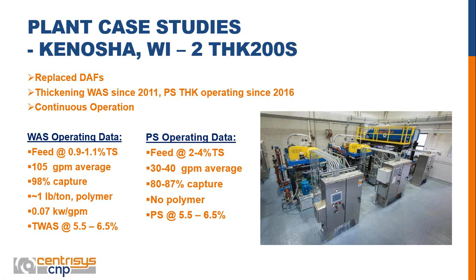Producing typically about 6% solids. Currently, they're not running that machine with polymer either, and they're taking a lower capture rate because they've decided from a cost standpoint it's more efficient for them to treat that return cycle in their aeration basins than it is to add the polymer. Again, you could add a little bit of polymer. In this case, it might be closer to 3 or 4 pounds per ton, and you could get that to 95% capture. All right, we'll move on.